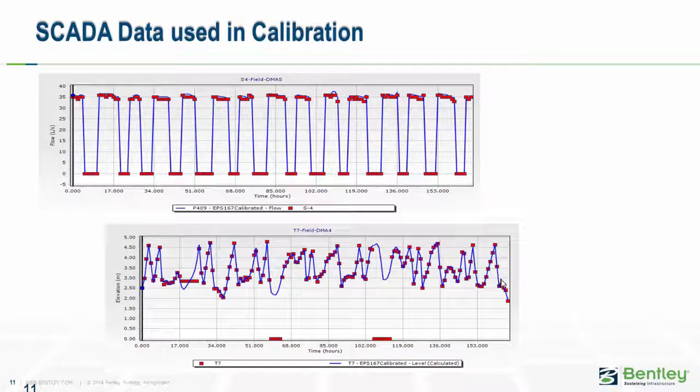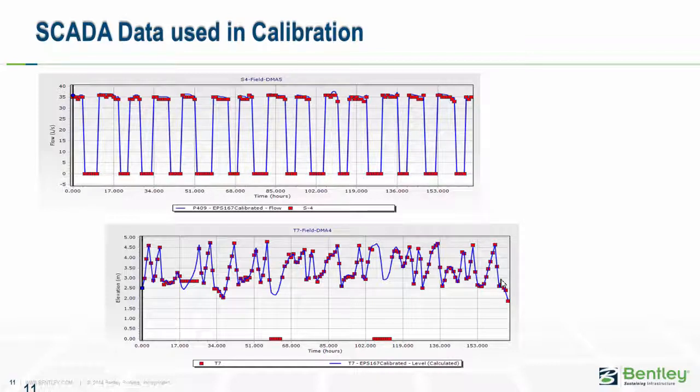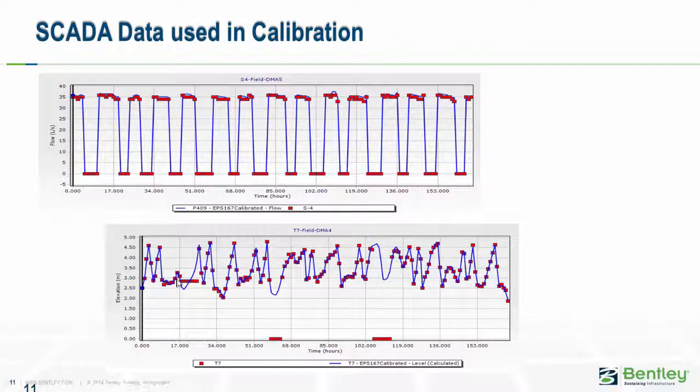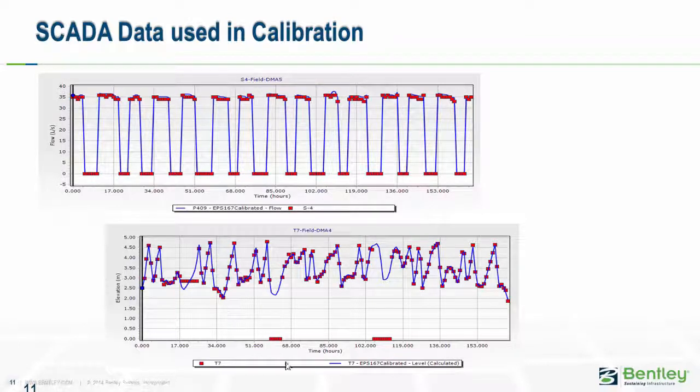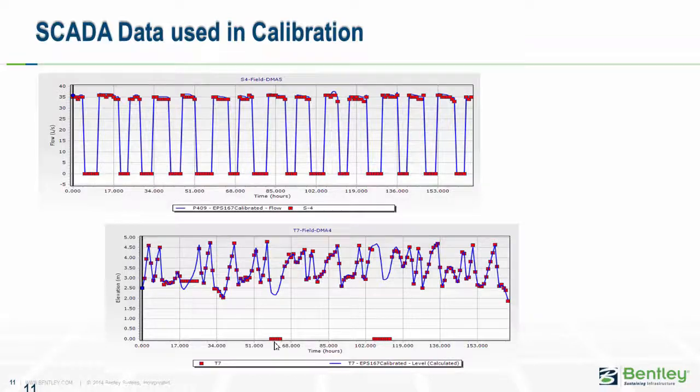Here's an example of using the data in calibration. Notice the red dots are the SCADA signals and sometimes they drop out. SCADA systems aren't always perfect. Neither are models of course, but it takes a lot of work to get the SCADA system and model to match. There are times when they're not going to match, when the SCADA signal might be latched on to a given value, or it may just drop out and not contain a value at all, or maybe something like NAN, not a number.